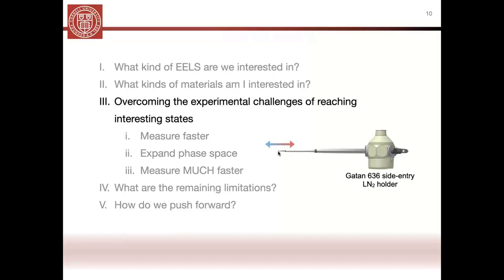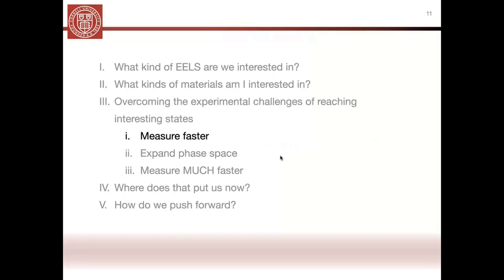And so with this thermal gradient from very cold to much warmer, you can have a sort of perpetually changing thermal contraction and expansion of this long sample rod. So what that does is it gives you relatively large drift, for these length scales, at the sample position while you're trying to measure.